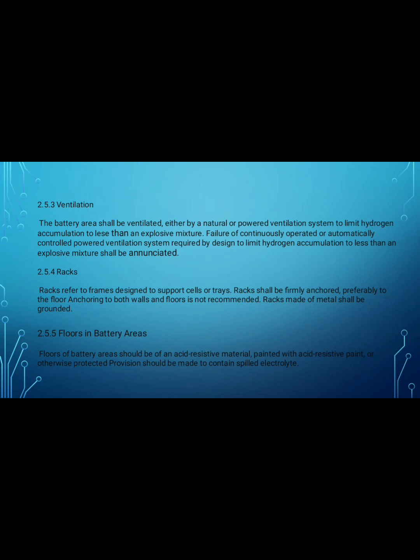2.5.4 Racks. Racks refers to frames designed to support cells or trays. Racks shall be firmly anchored, preferably to the floor; anchoring to both walls and floors is not recommended. Racks made of metal shall be grounded.